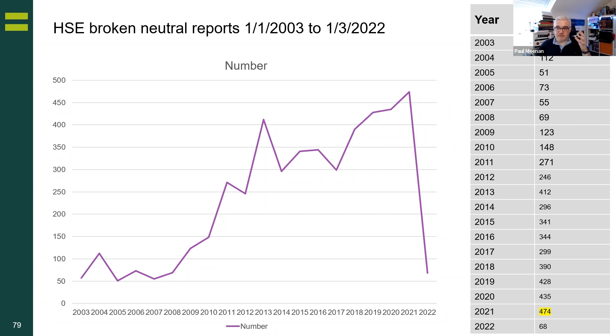My advice, if you're working on a DNO head, use a contact voltage indicator. Make sure you're wearing gloves and have a clamp meter. And that's the recommendation in GN3 for the clamp meter to check for this. Not necessarily saying it's dangerous, but it's something that the networks need to manage.